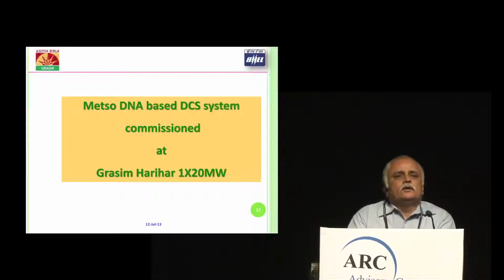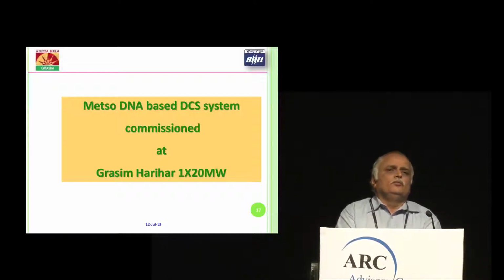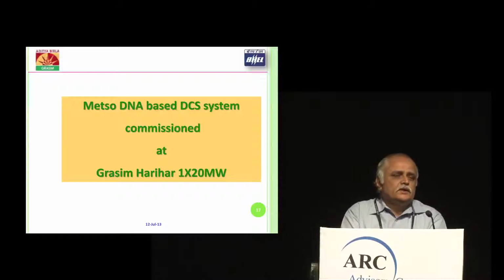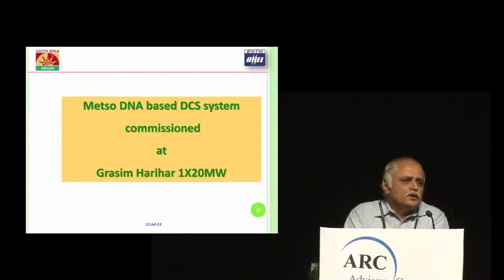As it was said, of course, we have been supplying a lot of equipment for utility plants, larger power plants, much larger combined cycle plants, cogen plants, and other things. However, when we want to design a control system for a captive power plant, the control requirements are very stringent, and the implementation has to be very precise. Because when you're doing a large capacity utility plant, it has to only produce power and be connected to the grid. Once it is connected to the grid, it has to supply the power.